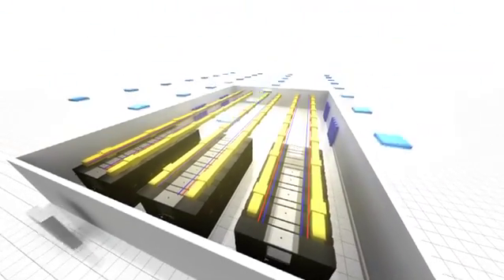We really needed a room neutral design that wasn't going to upset some of the tape libraries we had, some of the switches that couldn't cope with having a room heat up. We looked at hot aisle containment, we looked at cold aisle containment and realised that hot aisle containment was the only way that we were going to be able to achieve this in the data centre.